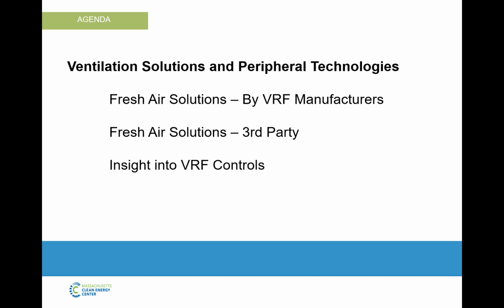Okay, so we've already mentioned, again, the words fresh air, ventilation air, outside air. They all refer to the same thing. Basically, any new building now or any major retrofit needs to basically meet a certain version of the ASHRAE 62.1, which is the general standard around how much fresh air you got to bring into a building, depending on occupancy, size, and all that. So this building here also has fresh air. Majority of buildings have that.